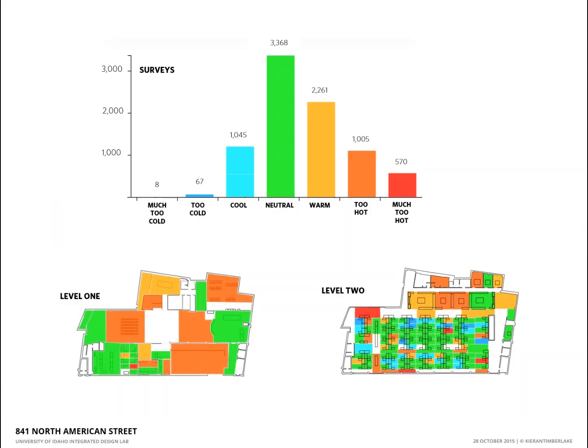So every day, a survey goes out to the staff, actually several times a day, and asks them, are you too hot, too cold, just right, what have you? And what are you wearing? Where are you located? So we're able to get spatially and employee-specific data, including the clothing factor, multiple times throughout the day. And we're able to feed this back to the temperature data point that we have for every location. And because we know where our employee is located, we know the temperature of all the surfaces surrounding that employee, and we know the emissivity of those surfaces, we can create a radiant temperature map as well as an ambient temperature map of the office.